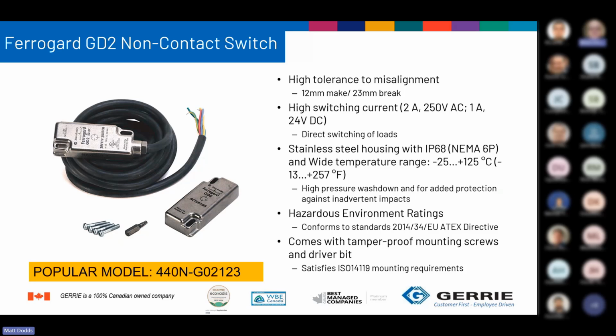I usually see these types of products on food processing equipment, say like a dough mixer or something. They have a stainless steel housing with an IP68 rating, NEMA 6P, up to 125 degrees C and down to negative 25. And then they also have hazardous environmental ratings, so again, for ATEX approvals. And they come with tamper-proof mounting screws and a driver bit. So again, this satisfies the requirements.